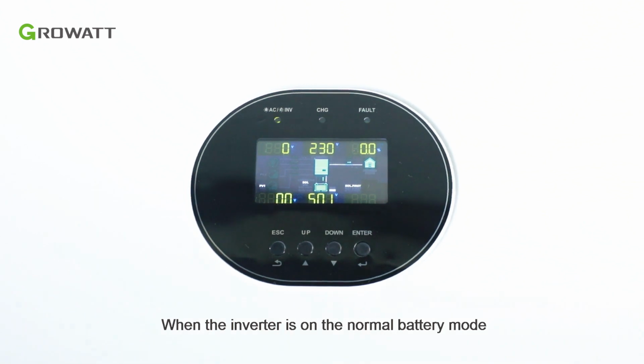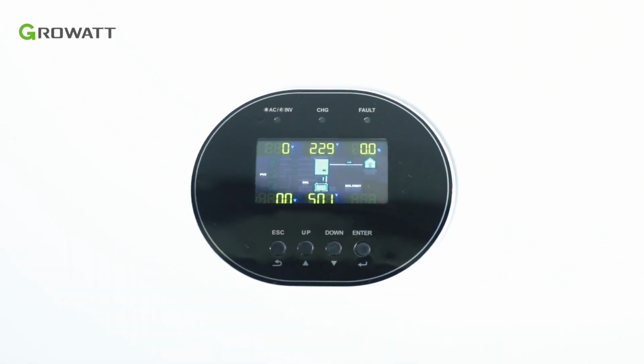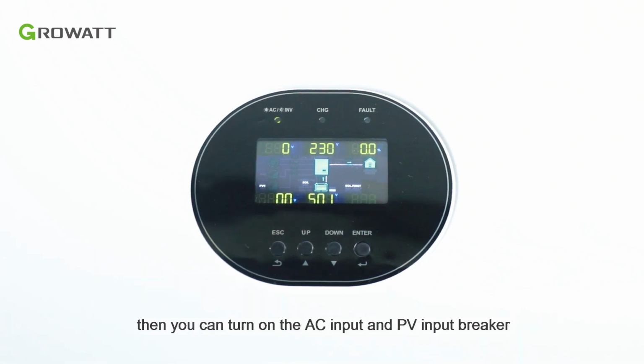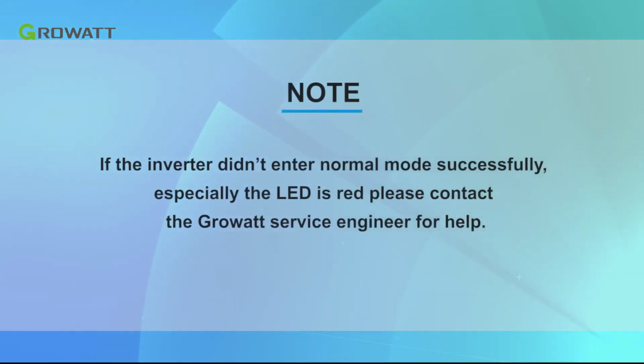When the inverter is in normal battery mode, the screen shows normal and the LED is green. Then you can turn on the AC input and PV input breakers. Note: if the inverter doesn't enter normal mode successfully, especially if the LED is red, please contact the Growatt service engineer for help.